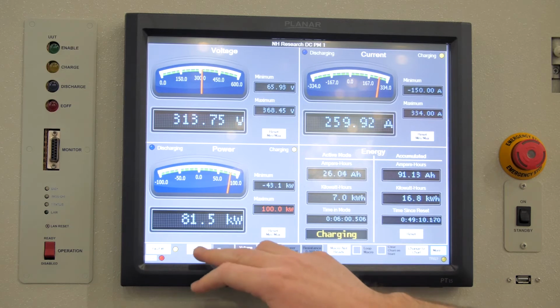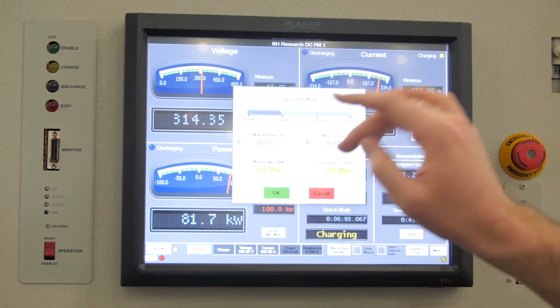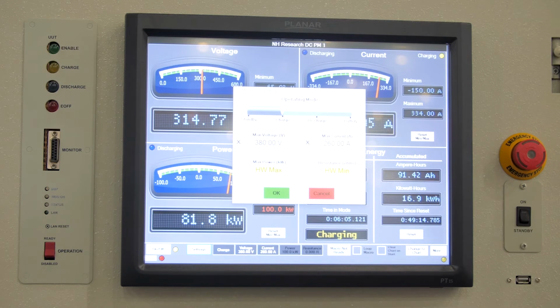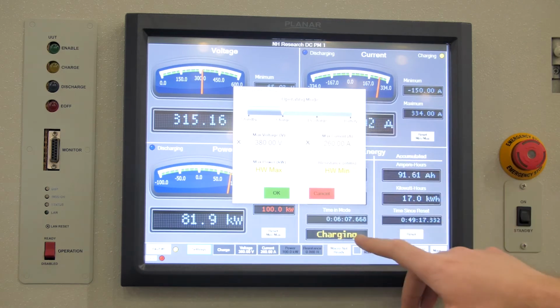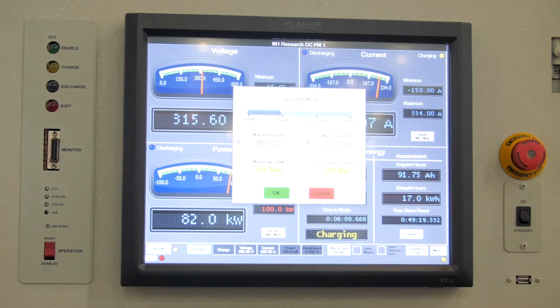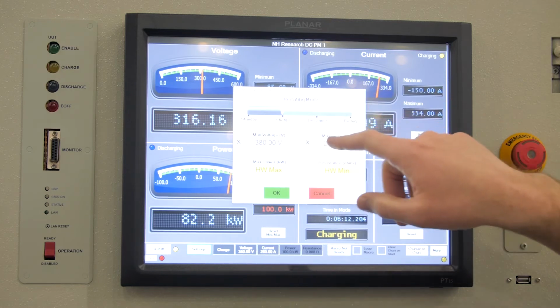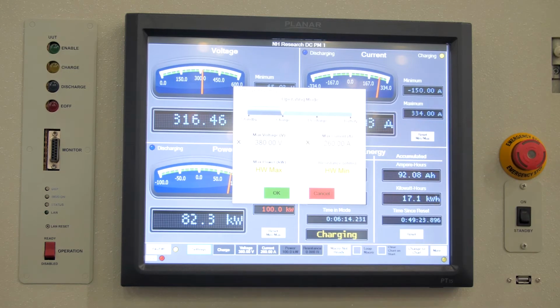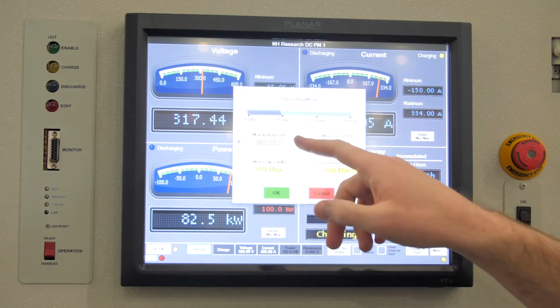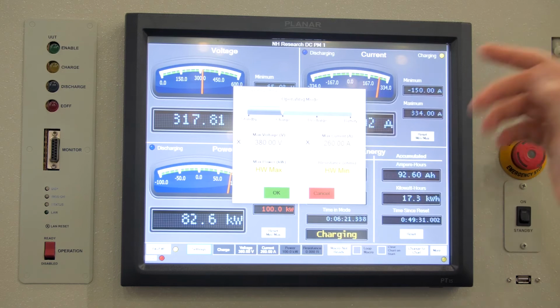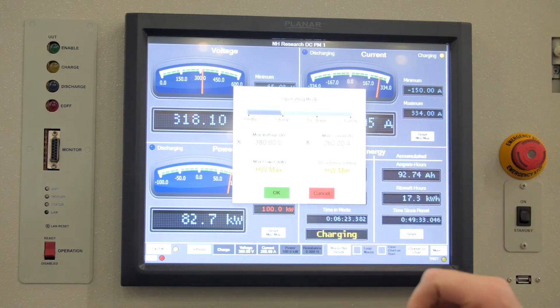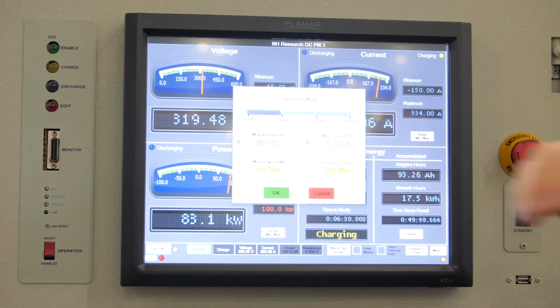As we go into the settings tab, this is where you determine that operating mode I was mentioning. So right now we're in a charging state, as in we're charging a battery, but there are a couple other modes here. Standby mode, this would just be, we're ready to run, but we're sitting at idle at this point. Your charge mode, again, charging the battery. Your discharge mode, that's going to be discharging the battery or sinking current to our system. And then you have your battery mode, again, for that inverter type test where you're trying to just set a voltage.